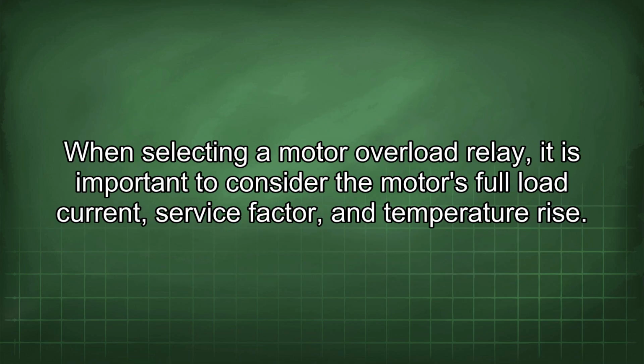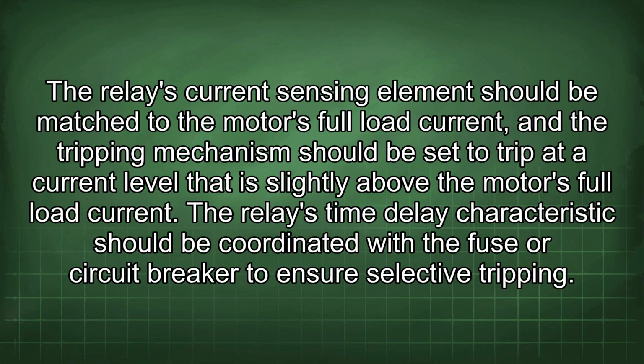When selecting a motor overload relay, it is important to consider the motor's full load current, service factor, and temperature rise. The relay's current sensing element should be matched to the motor's full load current, and the tripping mechanism should be set to trip at a current level that is slightly above the motor's full load current. The relay's time delay characteristic should be coordinated with the fuse or circuit breaker to ensure selective tripping.